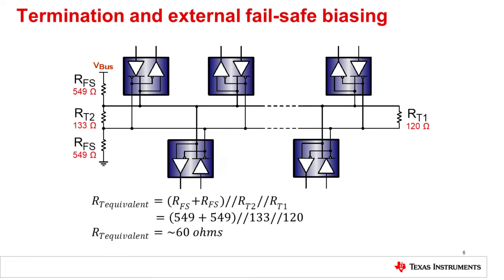Terminate the two furthest points of the bus with resistors equal to the characteristic impedance Z0 of the transmission cable. The termination resistance should match as closely as possible without dropping below 60 ohms, or 54 ohms if the transceiver's loading is included in the calculations.